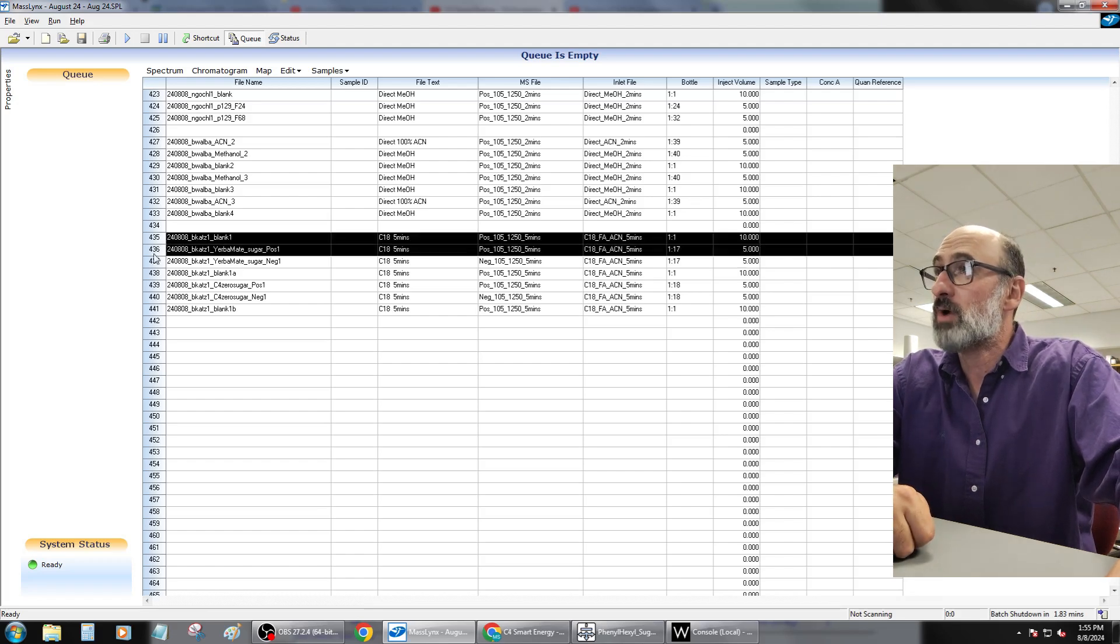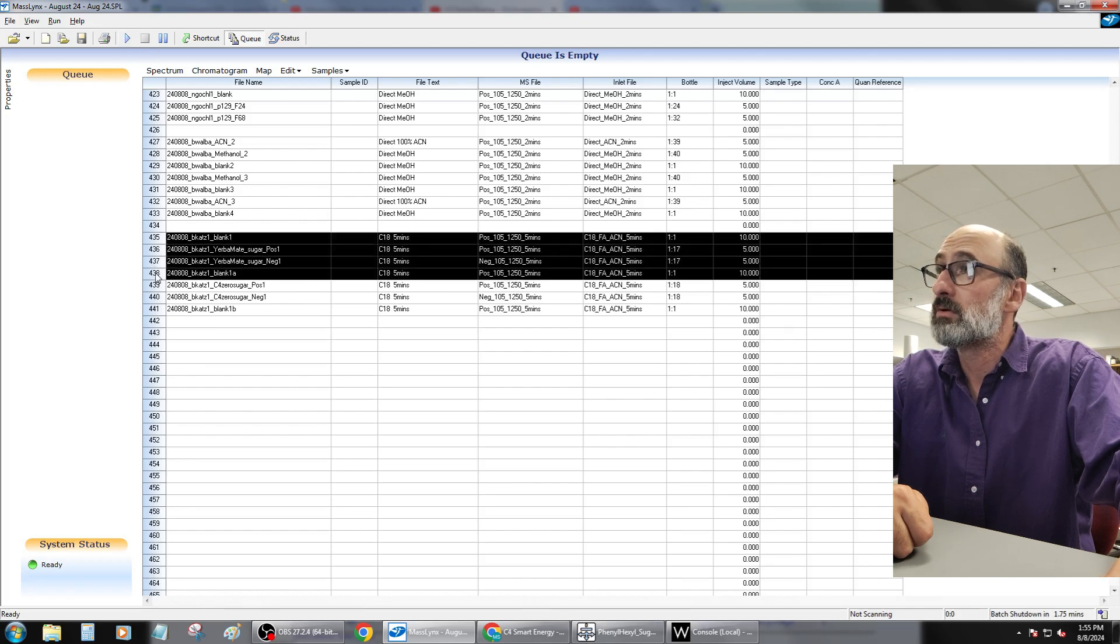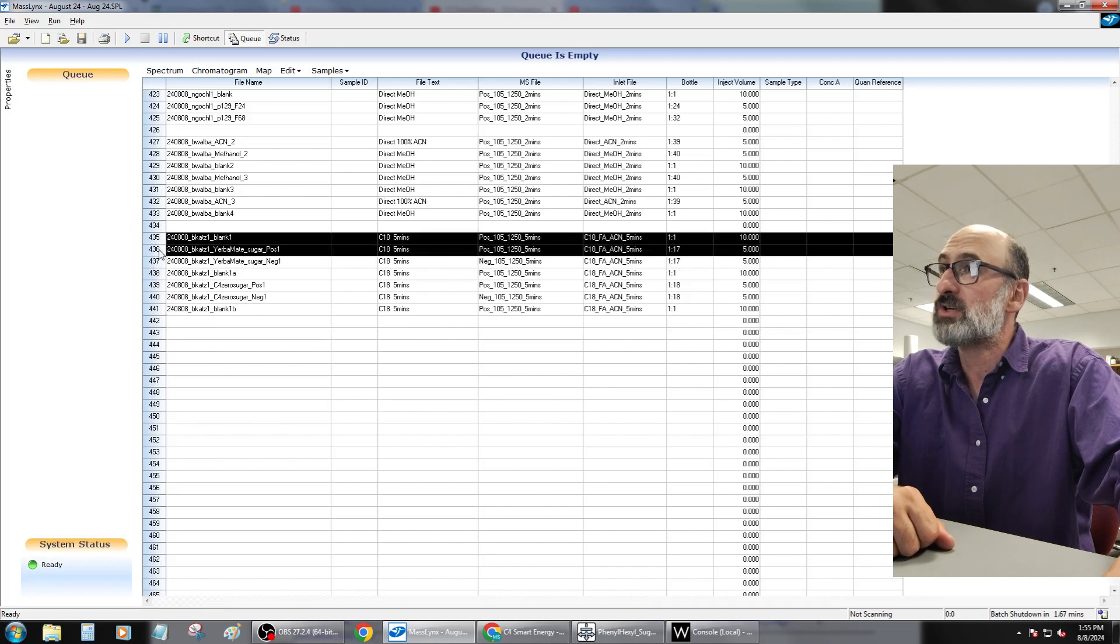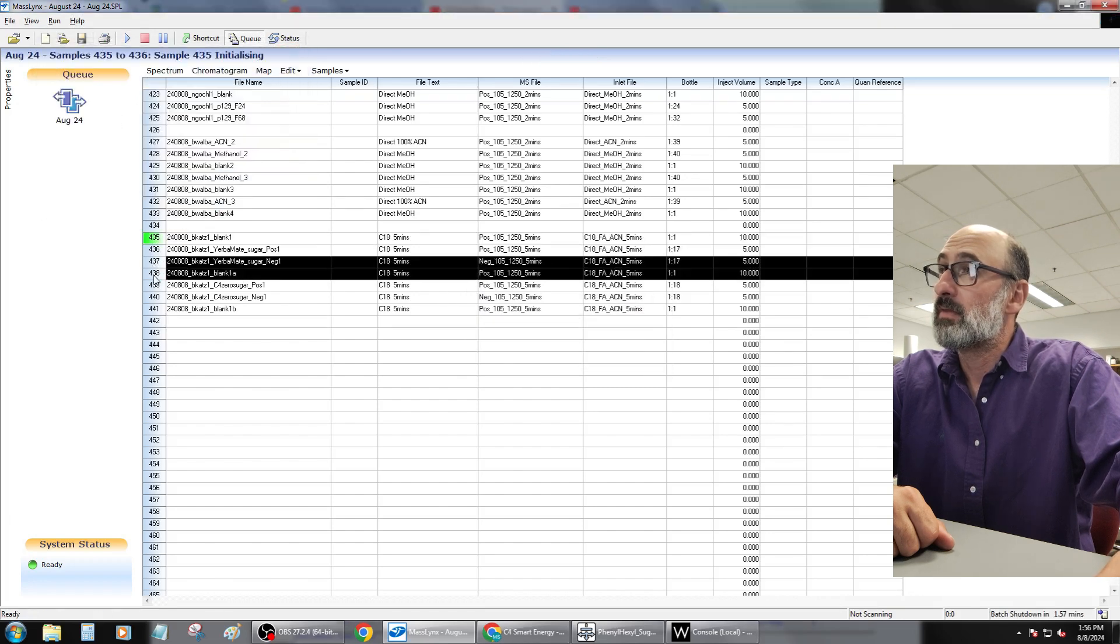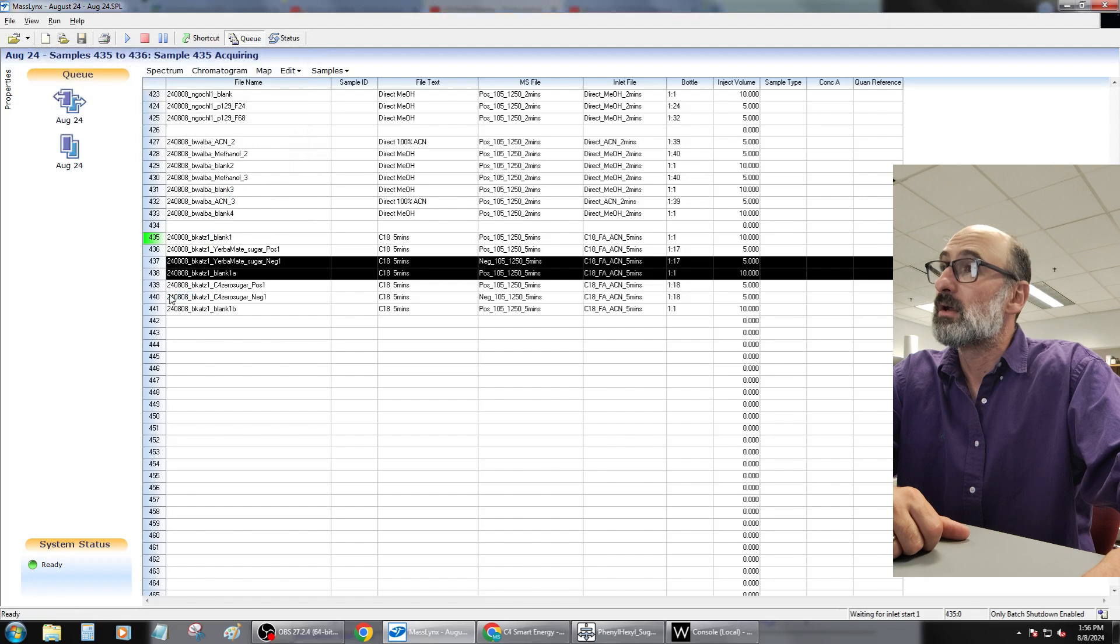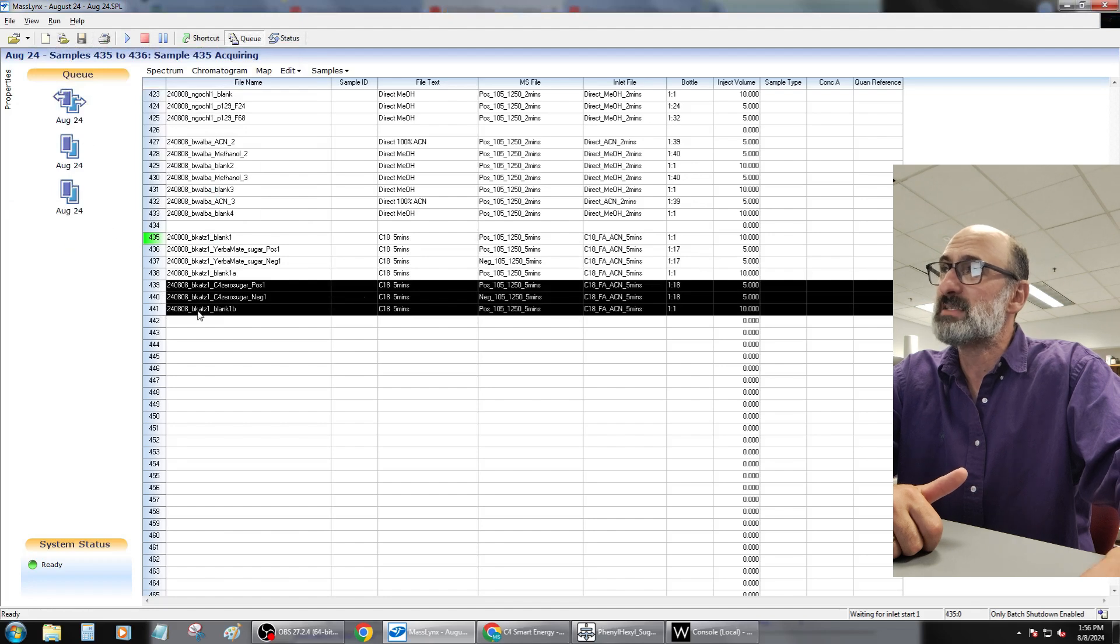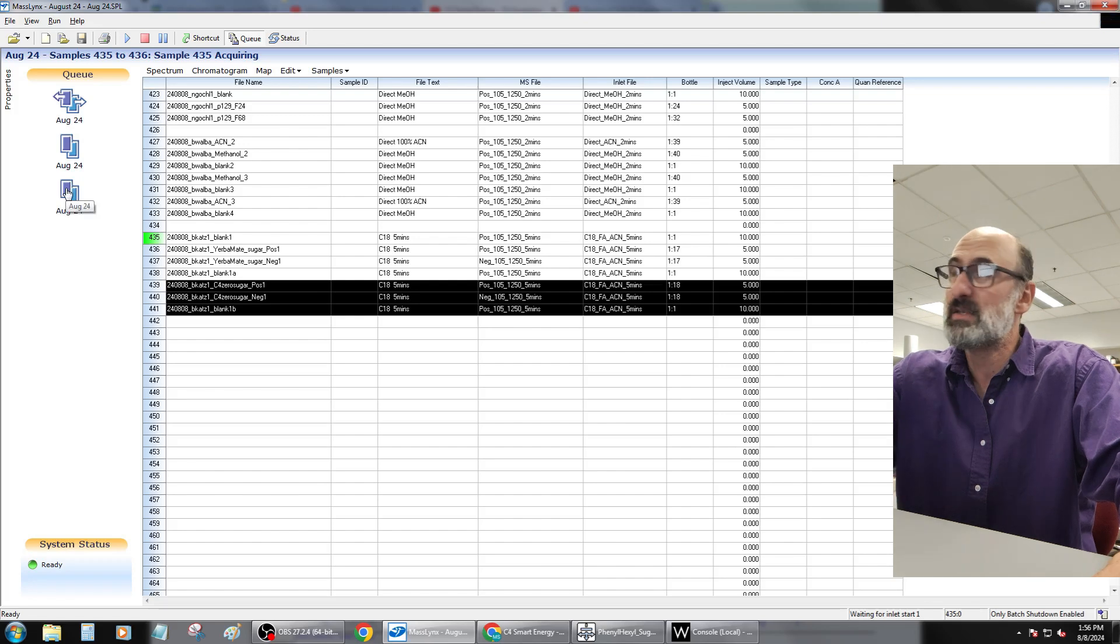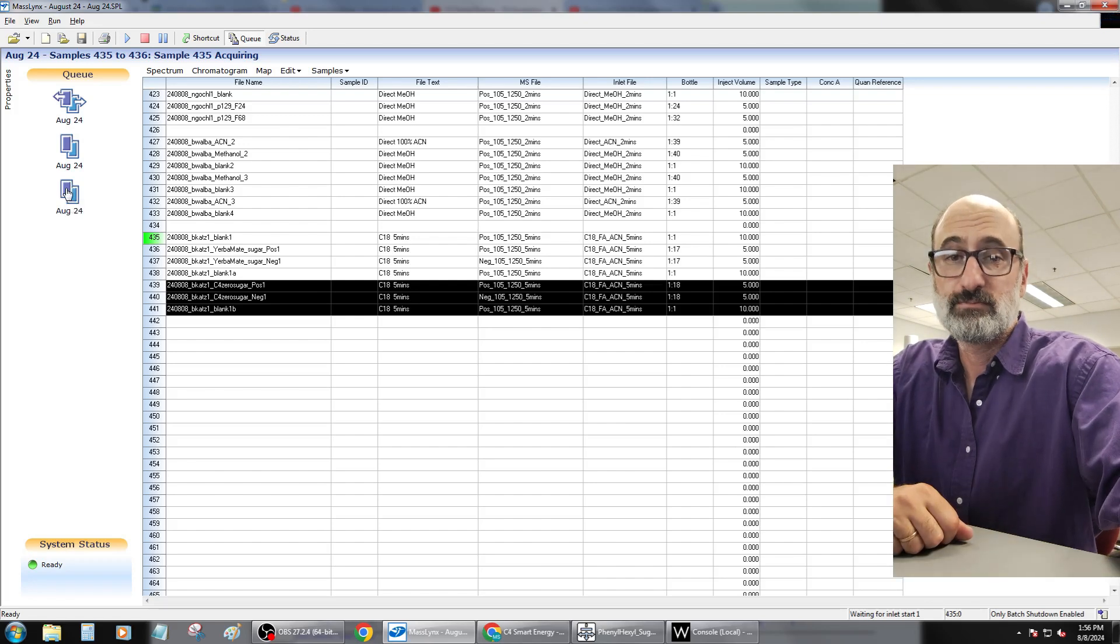So we'll go ahead and run these by hitting play—highlight the whole thing. I like to highlight it and run the first one by itself, actually, and then if that looks good, I'll go ahead and run the next part. Since we have that startup protocol, it should just turn itself on automatically. Then I'll send the next part, and then I'll send the next part, and so they're kind of all in separate queues. The reason I do that is if something messes up, it's easier to delete a queue that isn't running than to delete one that's in the middle of running, because that causes a lot more instrument stress. Alright, we'll wait for the data here.